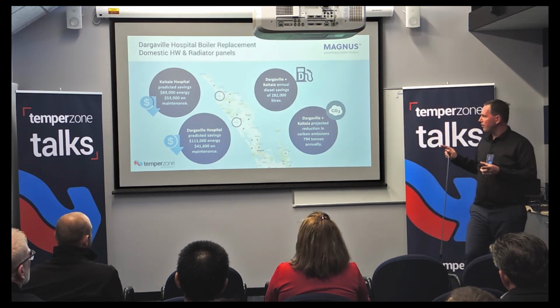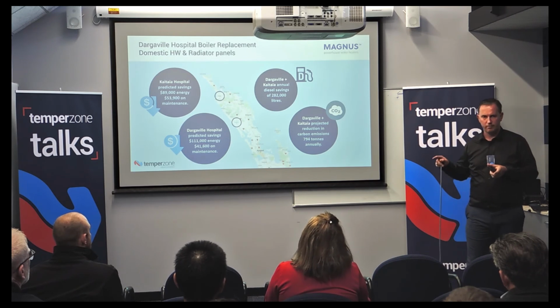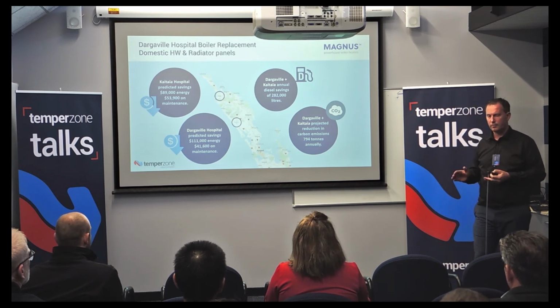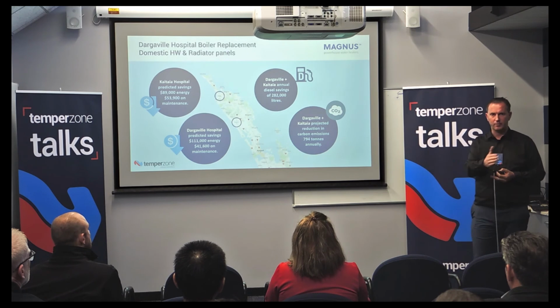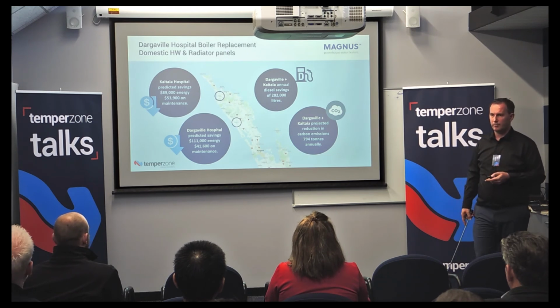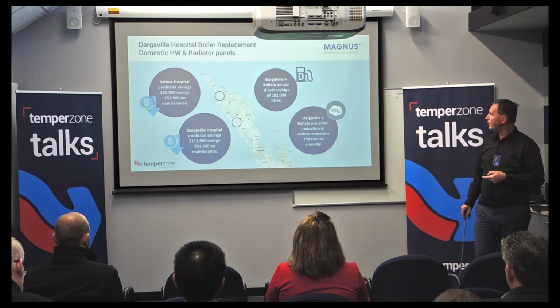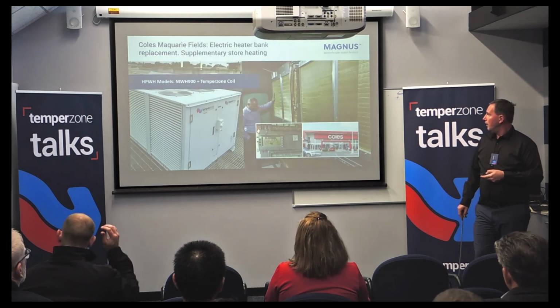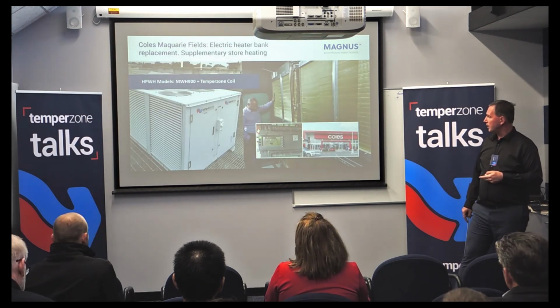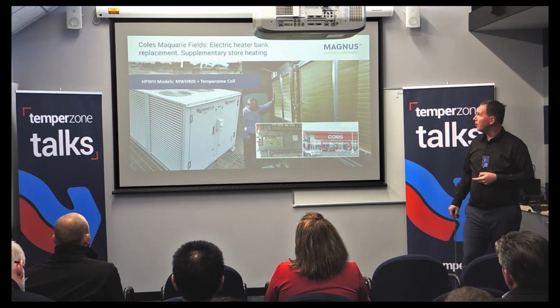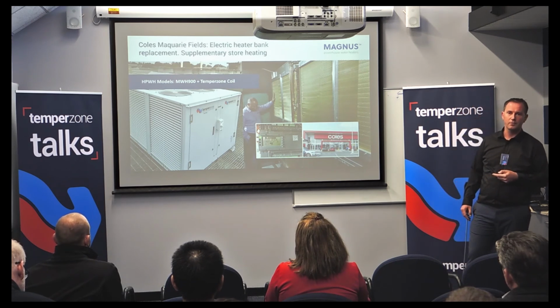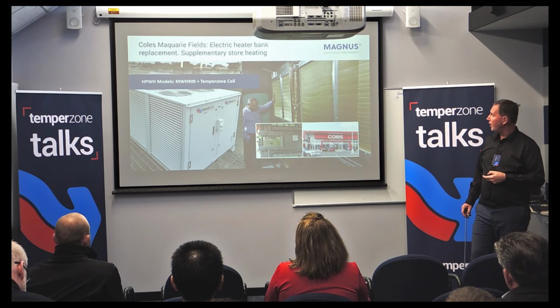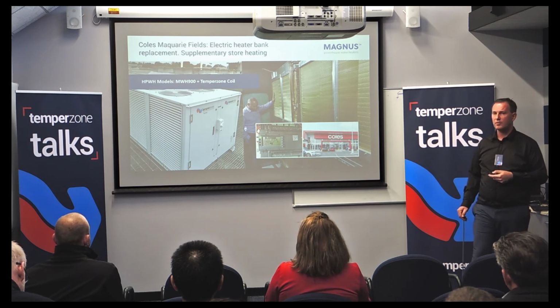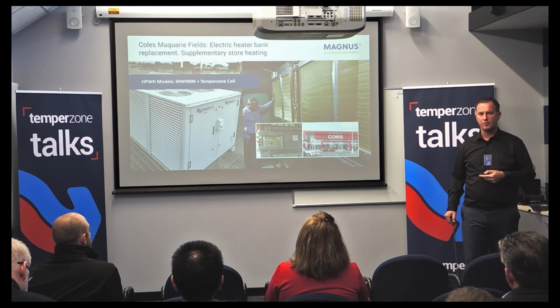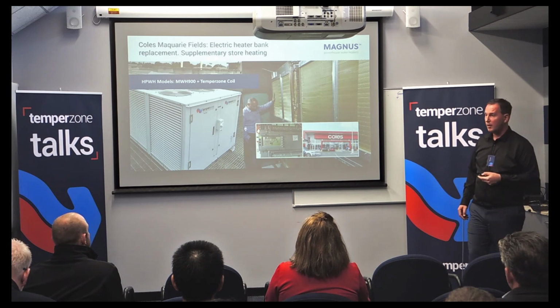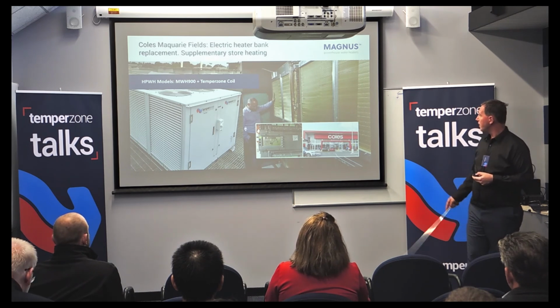Now the energy savings here aren't just the heat pumps, it's as much about the climate distribution. Another project was a Coles store in Sydney. Macquarie Fields is a very cold part of Sydney.